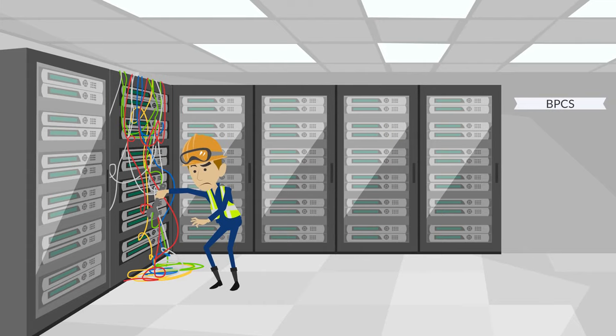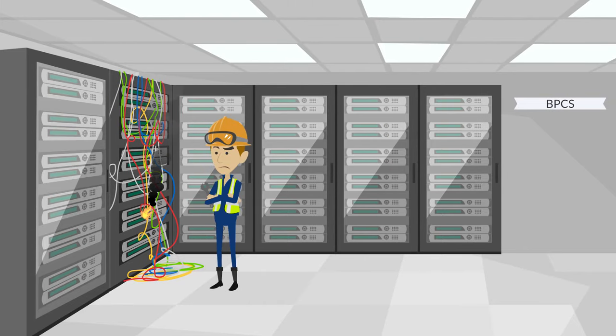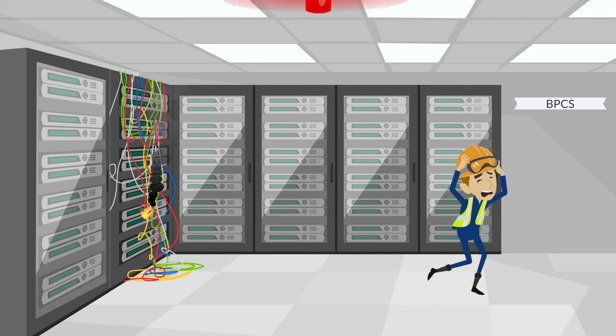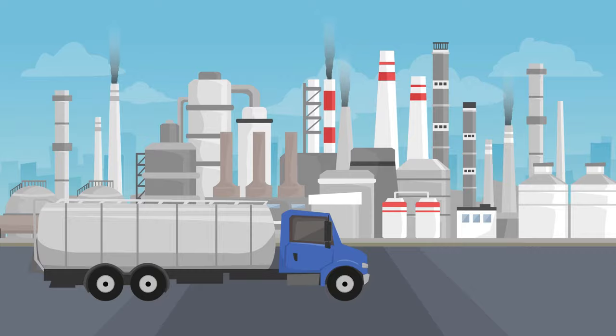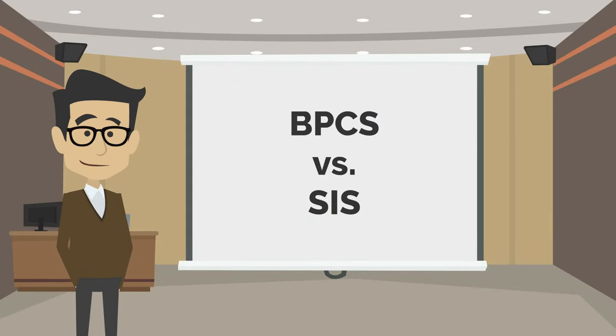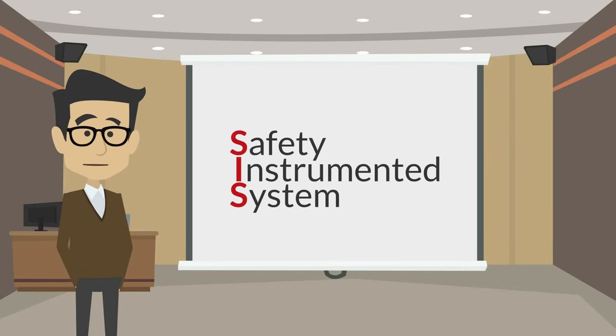But what happens if the BPCS controls malfunction? A safety instrumented system, or SIS, is an independent computing system from the BPCS, which monitors the system for potentially hazardous operating conditions.